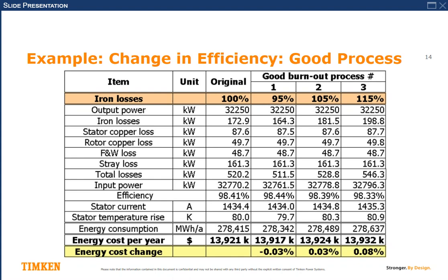We can calculate the input power; we take output power divided by input power, and we will see that there is a slight change in the efficiency of the machine, even after 3 burnouts, which in this class of machine should have been in the region of 100 years life. Obviously, with this first failure, we know why this occurred, but it should have been in the region of about 100 years.